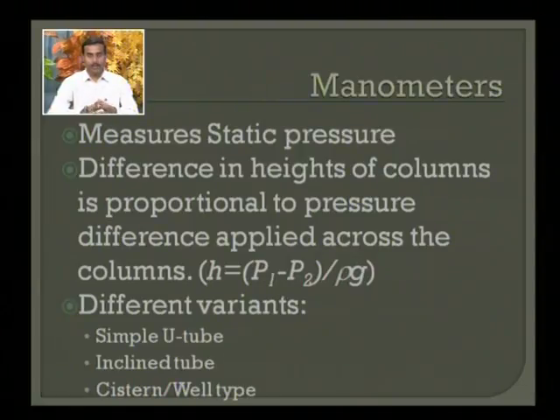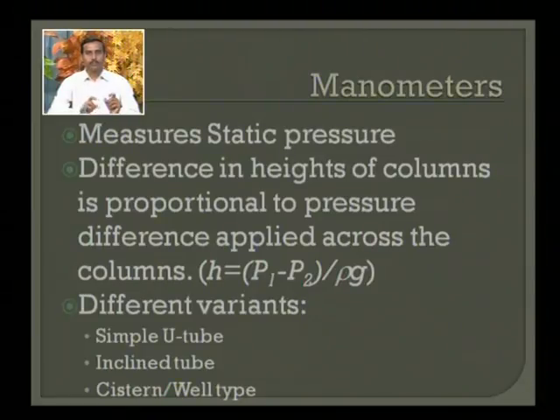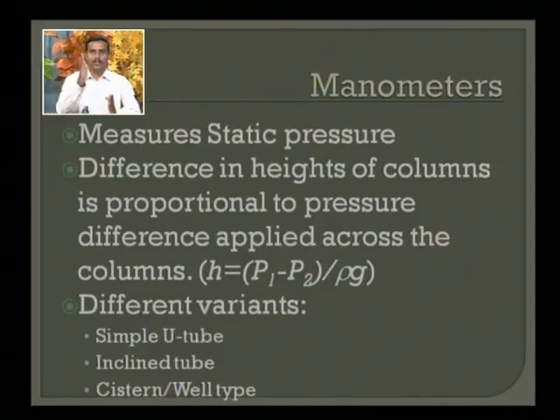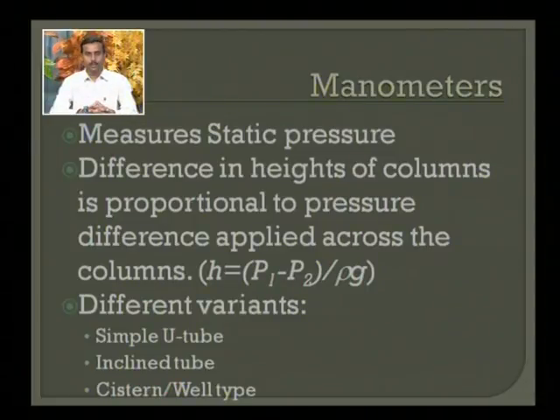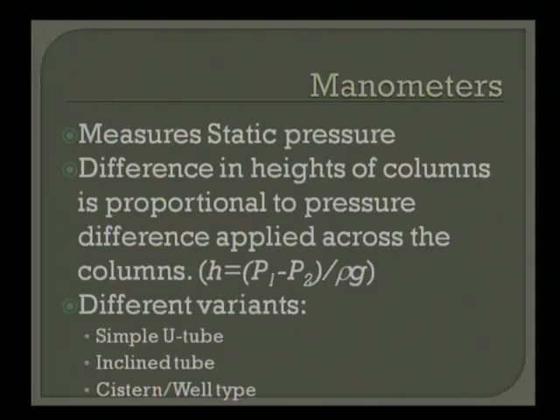Different variants of manometers are available. The simple U-tube is the one we are familiar with from physics laboratories. Another variant is the inclined tube manometer. The U-tube manometer has a resolution limited to about one millimeter. In the inclined tube, one tube is slanted at angle theta, and the diagonal measurement extends the range, providing comparatively larger resolution. The measurement technique remains the same, but the effective height being measured is extended.